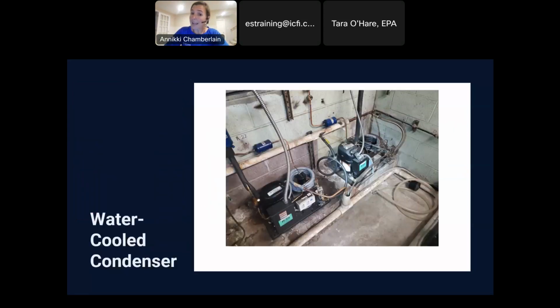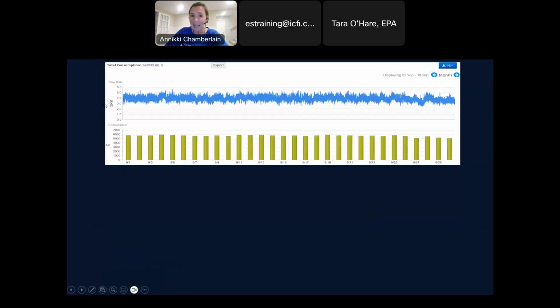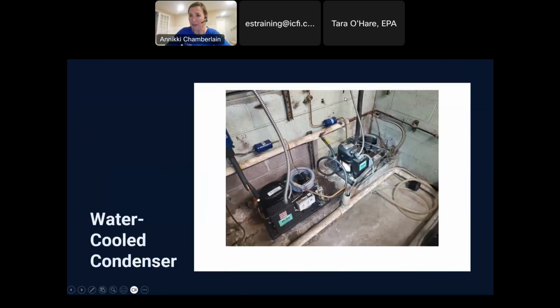Now let's look at another water-cooled system. This is for refrigeration units in a hospital. These are water-cooled condensers, so we clamped a meter on these, and this is 1 month now. It says the resolution has changed. This is still my gallons per minute, and now we're into gallons per day. This thing is just running completely straight, meaning the valves have failed.